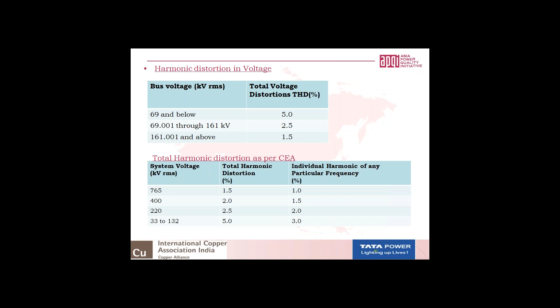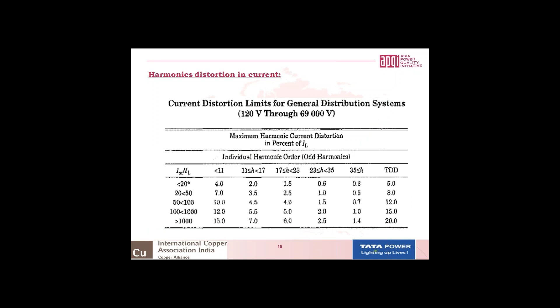For systems between 220 kV and 400 kV, the permitted THD is 2%, and the individual limit for a specific harmonic is 1.5%. For systems up to 220 kV, it is 2.5% and 2% respectively, whereas for systems between 33 kV and 132 kV, the permitted THD is 5%, and the individual harmonic level allowed is up to 3%. The harmonic distortion in current wave permitted as per the IEEE norms is given in this table. This is taken from IEEE and is available for reference on the IEEE website.